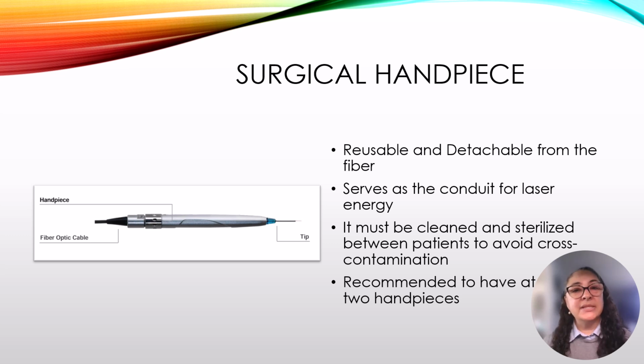The surgical handpiece is reusable and detachable from the fiber optic cable. The handpiece serves as a conduit for laser energy, directing it from the laser through the fiber optic cable and out the tip. You'll use the tips to aim and apply the laser energy. It often includes interchangeable tips for different procedures. We will cover the different types of laser tips further in the module.